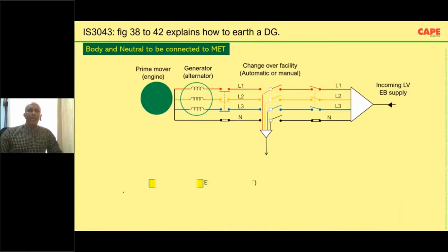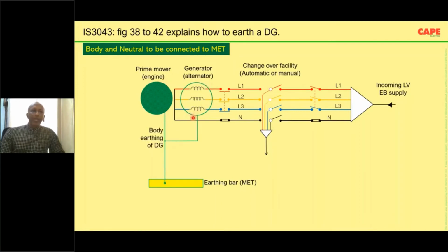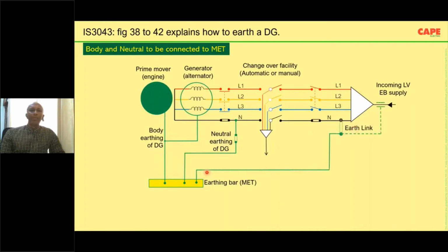Now, how do you do that? You can see this picture in IS 3043, figures 38 to 42. You can see the same picture here. On this side you have the engine, the prime mover, and this is the alternator. This is actually a generator. The generator body is connected to a bus bar, the earth bus bar. The neutral of the generator is connected to the same bus bar. The incoming EB supply is also connected to the same bus bar. On the outgoing side, the load side electrical apparatus is also connected to the earth bus bar.